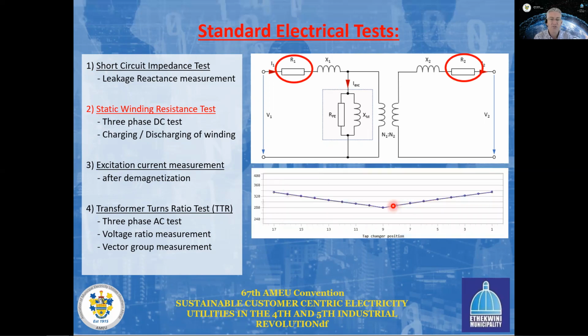The typical test results would look something like this, where we plot the winding resistance for each tap position of that transformer. Firstly, all 3 phases should be right on top of each other, because the winding resistance for each phase is identical if the transformer is good. Also, the plot should be a straight line, decreasing with increasing tap number. And if you have a tap reversal switch, you will see this V characteristic that you see here, where at the tap reversal point the resistances start increasing again, because we now switch the tap winding in the reverse orientation onto our main winding.